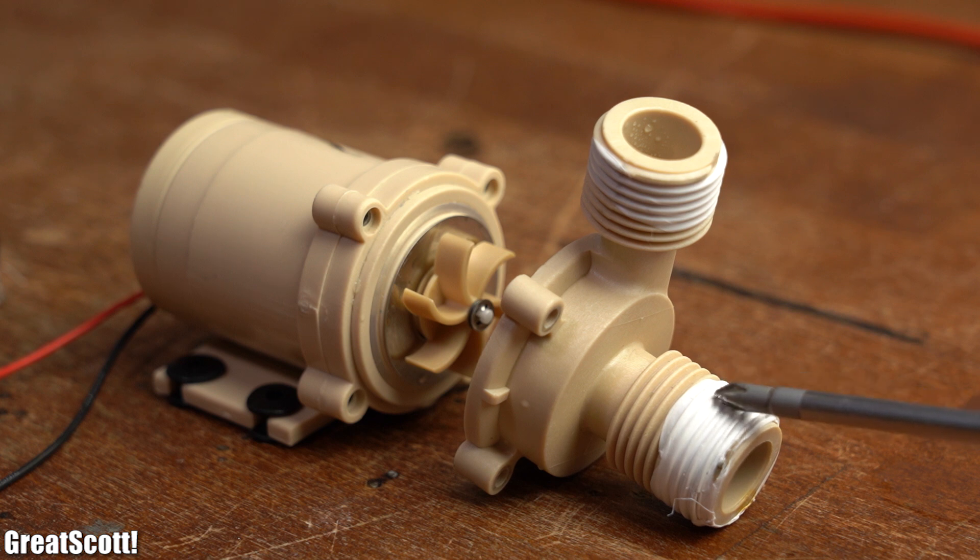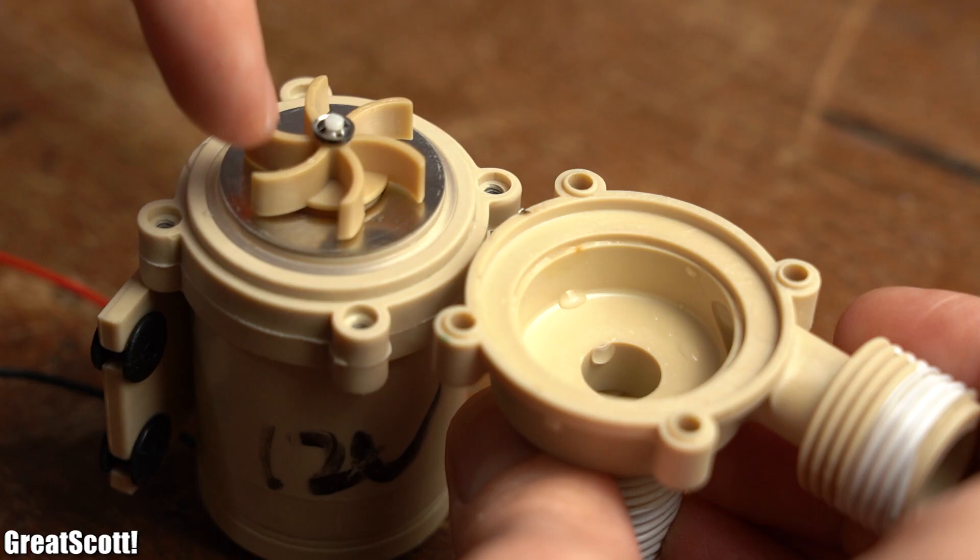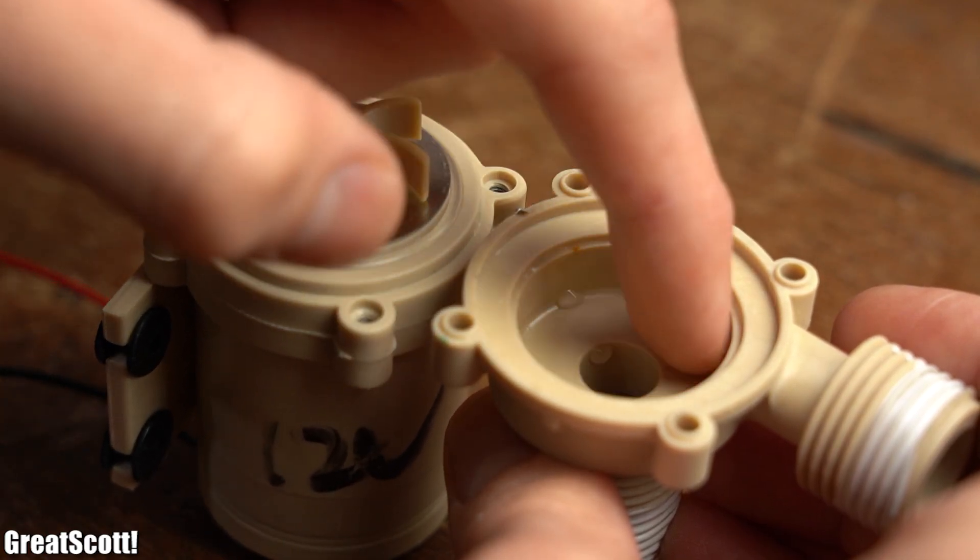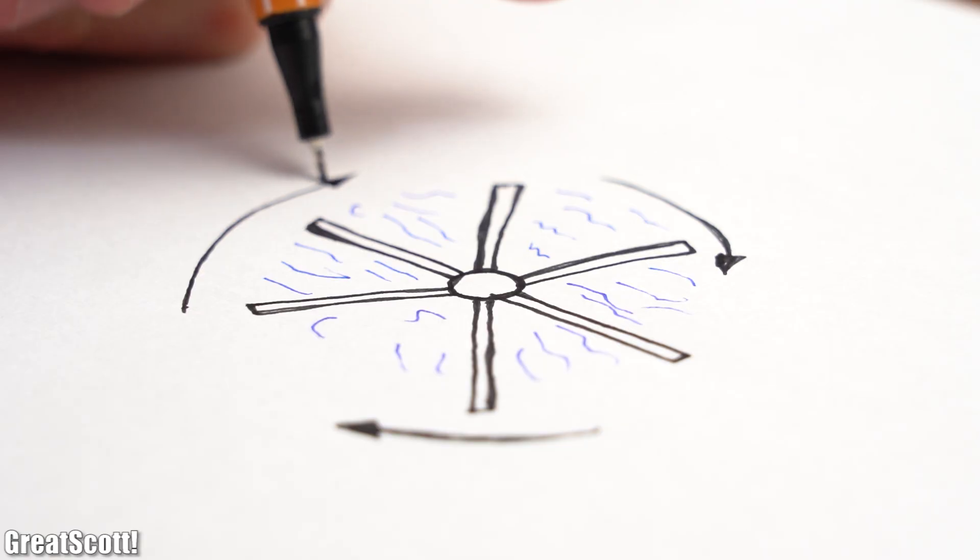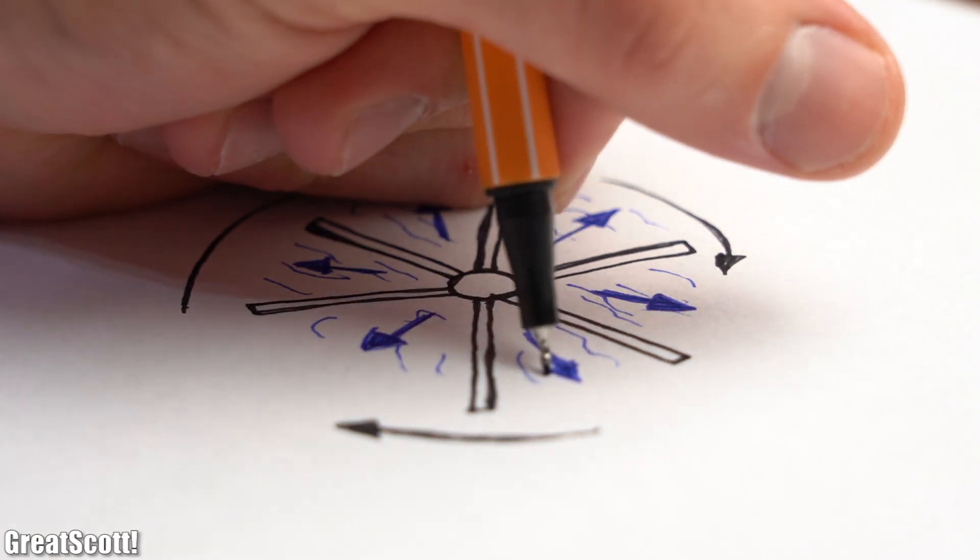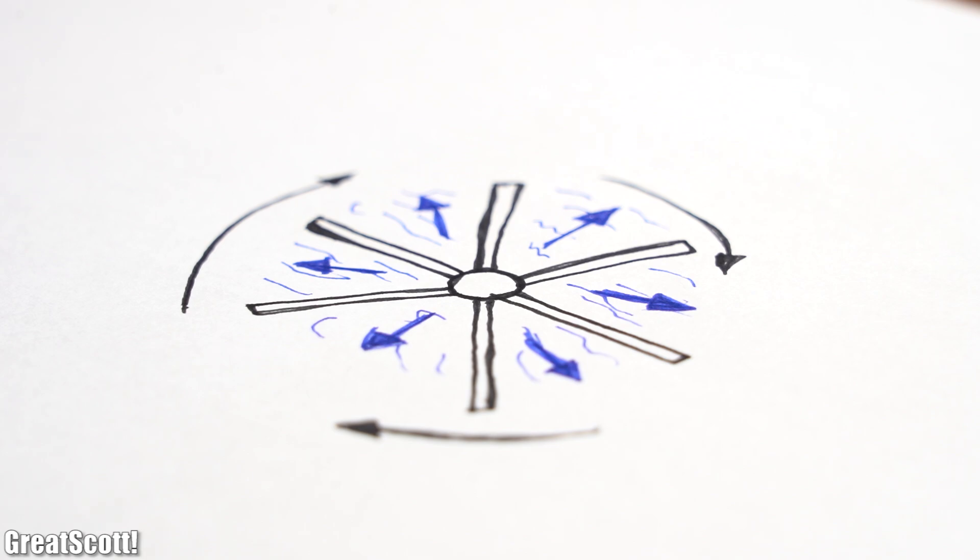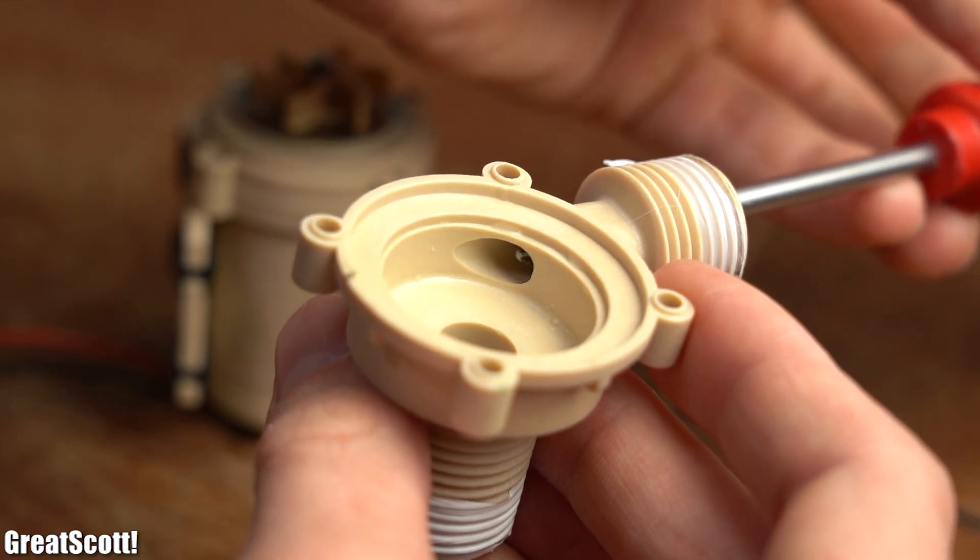After removing the front piece, we can see a wheel which was being turned by the utilized motor. So what happens is that the water enters through this hole and fills up the entire space around the wheel. And while the wheel is spinning, it accelerates the water which flows radially outwards and into a hole where it exits.